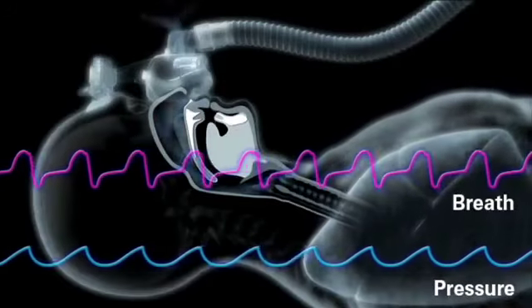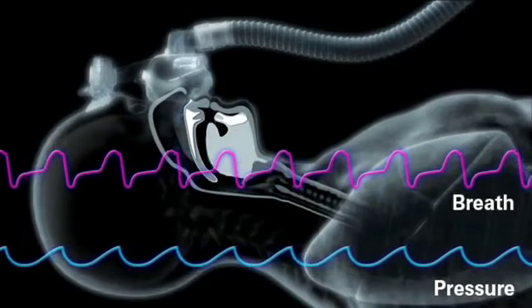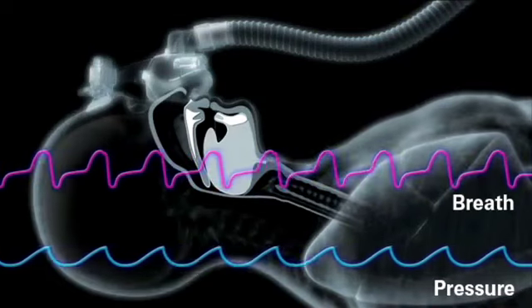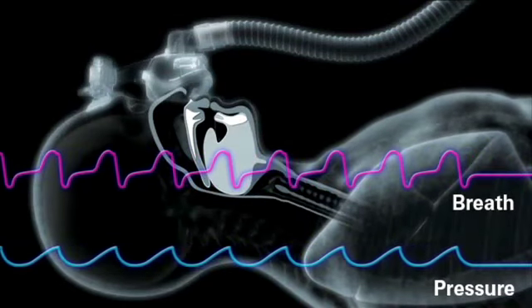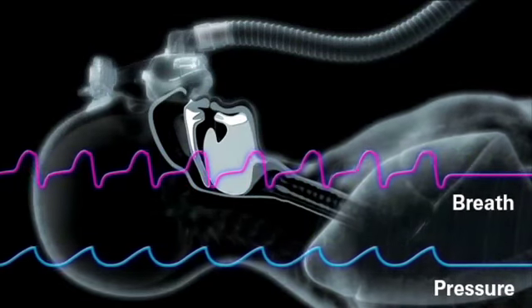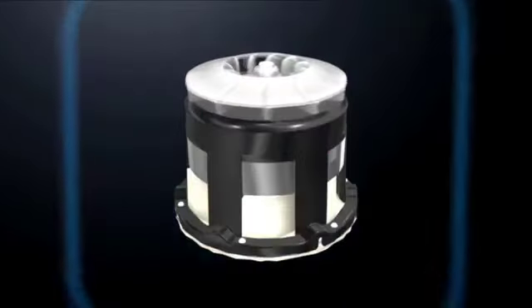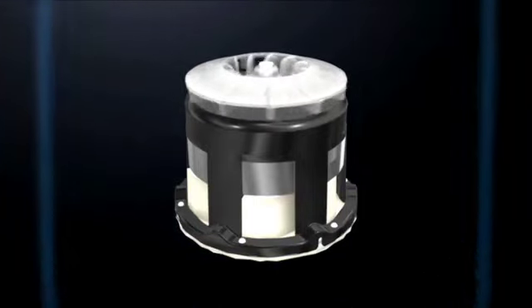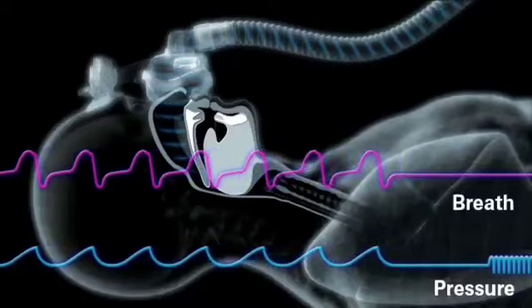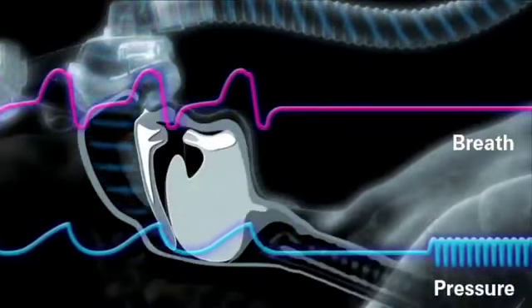ResMed's enhanced Autoset Algorithm can detect whether an apnea is obstructive or central. The device generates small amplitude pressure oscillations that flow down the tube and into the mask. The algorithm compares this pressure to its flow response.